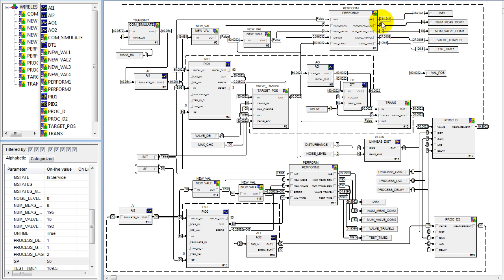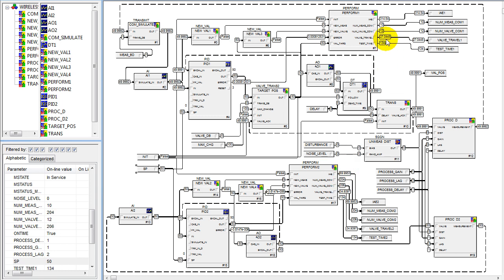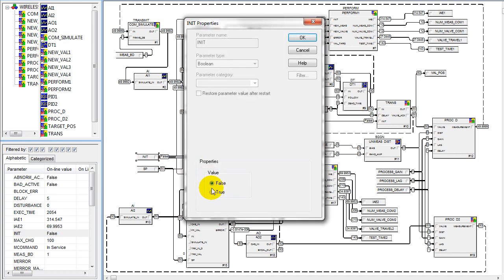Looking at the performance, we notice that the performance for wired and wireless is a little bit different — a little bit greater for wireless — but we only used 9 communicated values versus over 200 for the wired control. This demonstrates that with PID Plus we can do very effective control with very few communicated values.